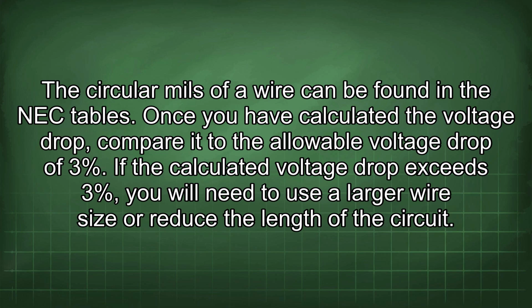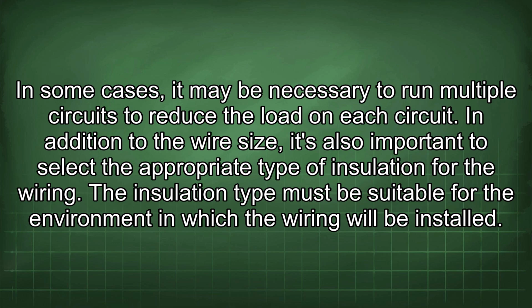Once you have calculated the voltage drop, compare it to the allowable voltage drop of 3%. If the calculated voltage drop exceeds 3%, you will need to use a larger wire size or reduce the length of the circuit. In some cases, it may be necessary to run multiple circuits to reduce the load on each circuit. In addition to the wire size, it's also important to select the appropriate type of insulation for the wiring.